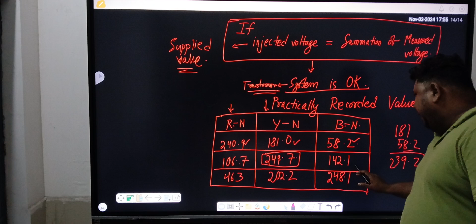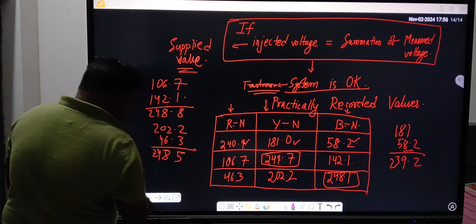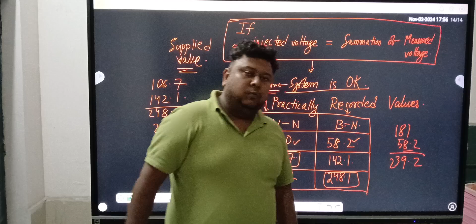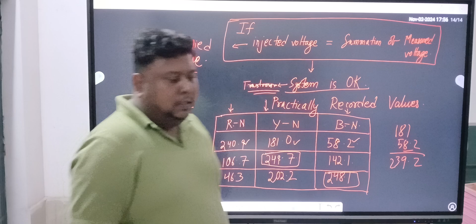Okay, no problem. Then again I have given the supply to B phase. You can check it here, 248.1. Now check whether these two values, 202.2 and 46.3, add up to that value. We are concluding with 248.5. So 248.5 and 248.1, no problem, it is okay. So we are getting approximate and near values to the measured phase values for the different phases, and in this way we can conclude that the magnetic balance test is successful and the system is okay.